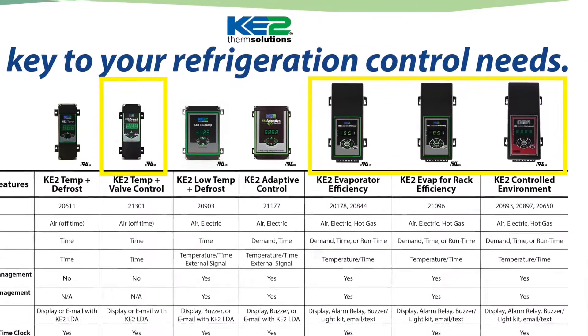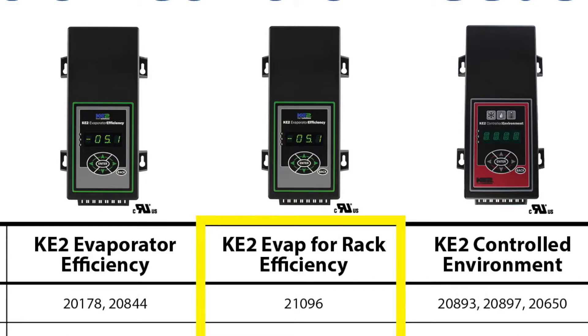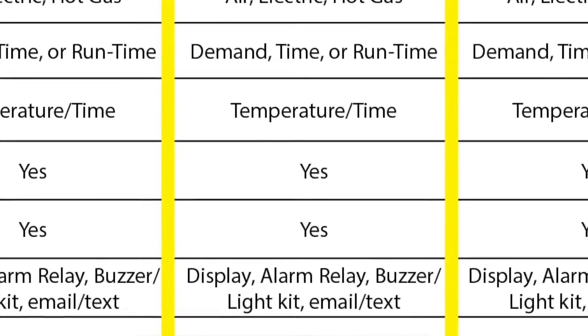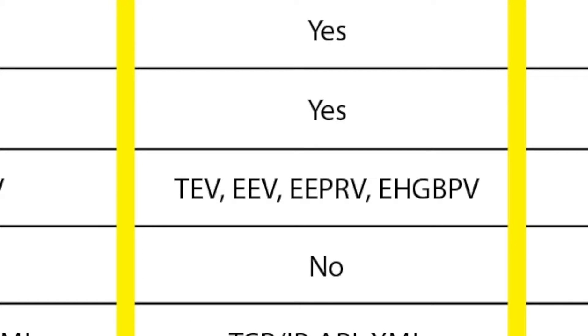Valve control varies from mechanical TEV for all of our controllers to controllers with the ability to control multiple electric valves. For example, the KE2 Evap for Rack Efficiency can control an EEV and an electronic pressure regulating valve or electronic hot gas bypass valve. Using the table to eliminate controllers based on these features will help you pinpoint the best controller fit for your application.